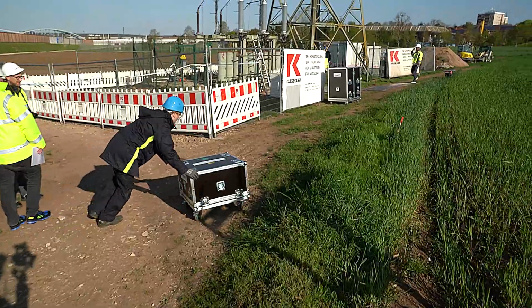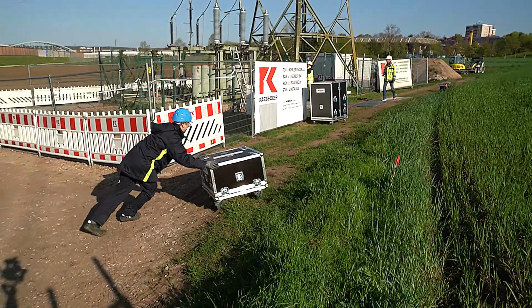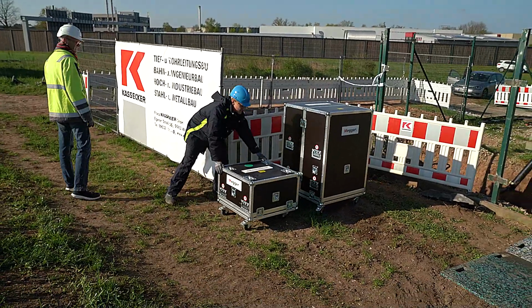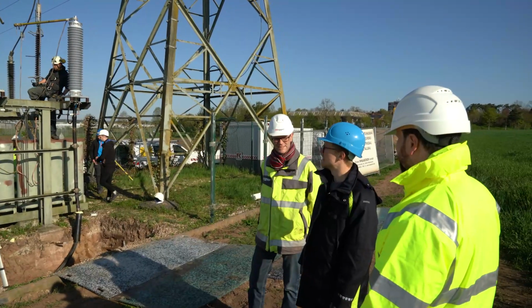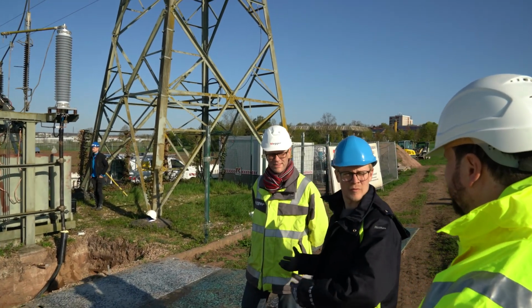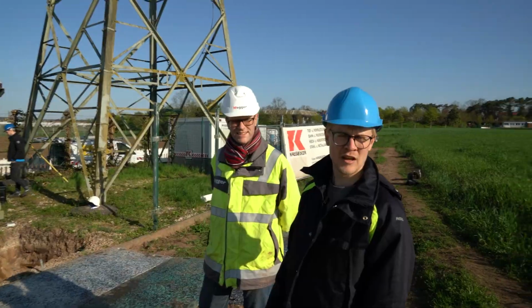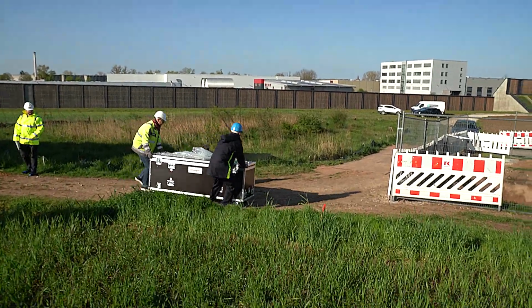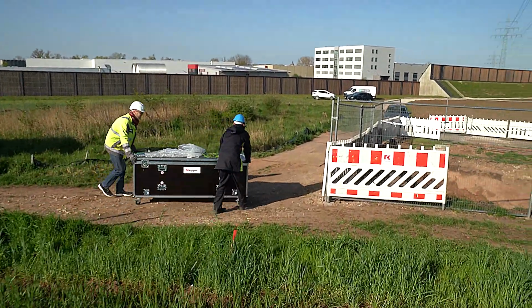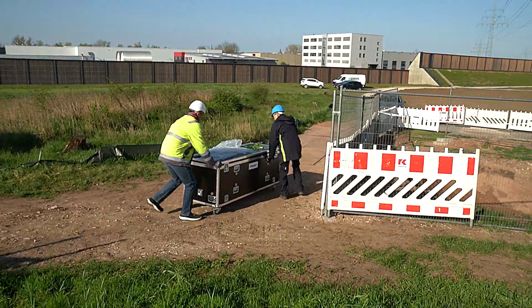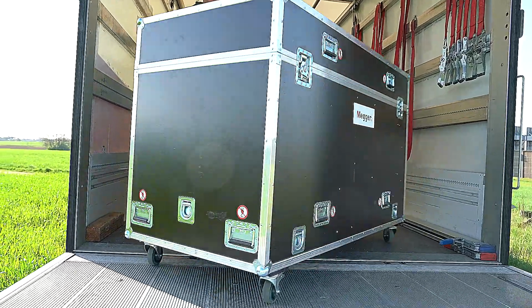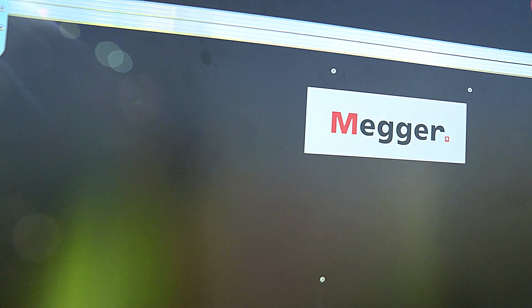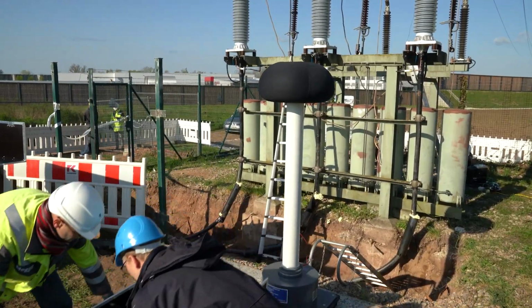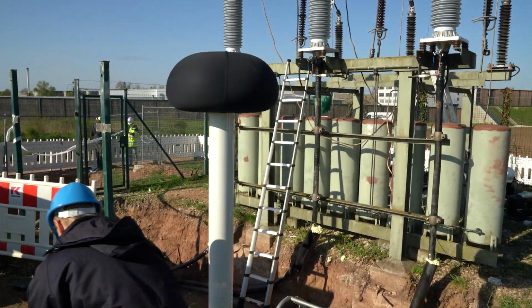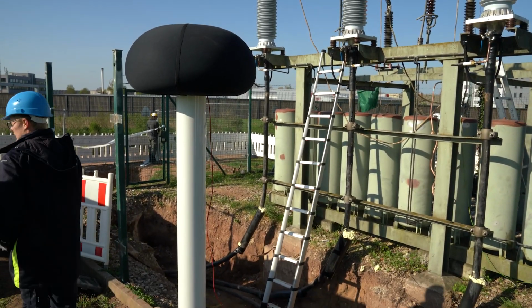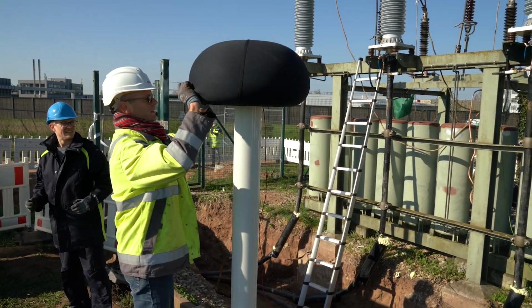For this, we will use our damped AC system. This system is used to perform on-site voltage testing and has the advantage of being very compact and quick to set up. This means that tests can be carried out within one day, as will be the case today. The system consists of 4 parts in total. There is a high-voltage power supply, a switch, an inductor or coils, and a coupling capacitor where the measuring signals are decoupled.